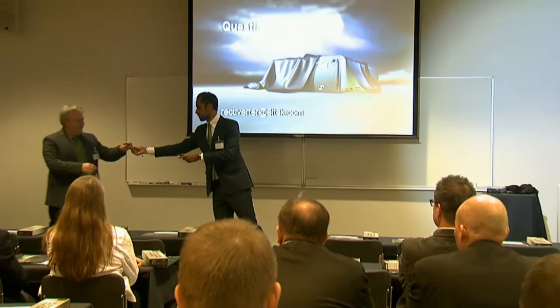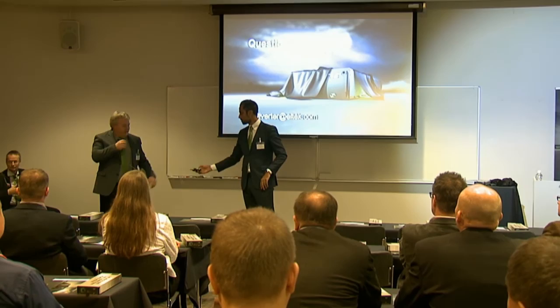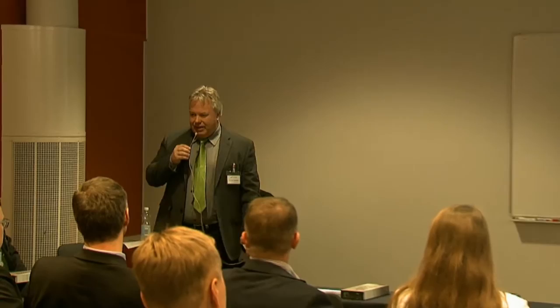Hello. Yes, thanks for the great presentation. Just a small question: does this have any new demands on batteries? Yeah, of course, you can use it with any type of batteries, because it's a normal rectifier that you charge your batteries with. But of course, if you go into, let's say, cyclic applications like the microgrids, then of course it's a challenge for the battery suppliers to have good batteries for such applications. Otherwise, if it's a standard backup application, then you can use normal lead acid batteries or whatever you like.